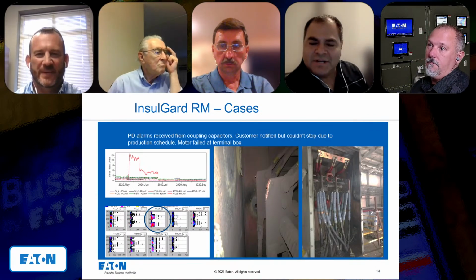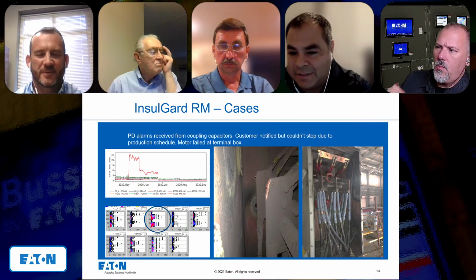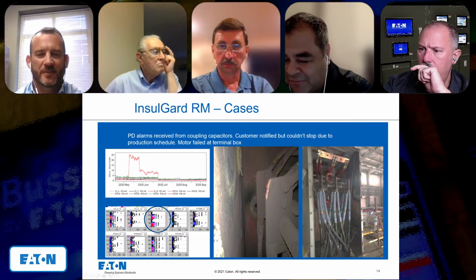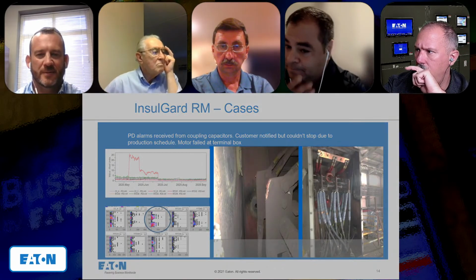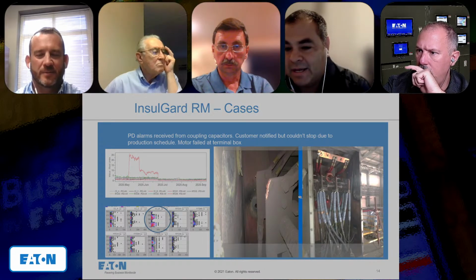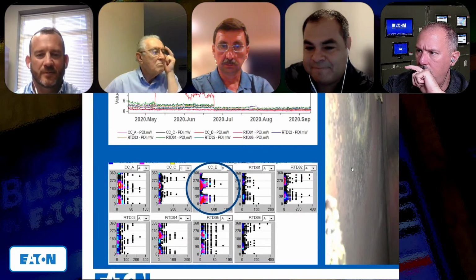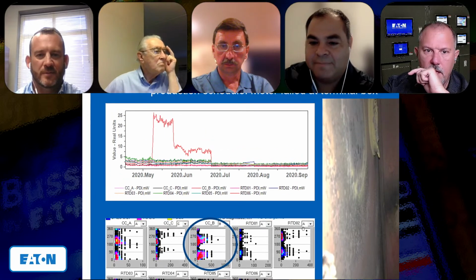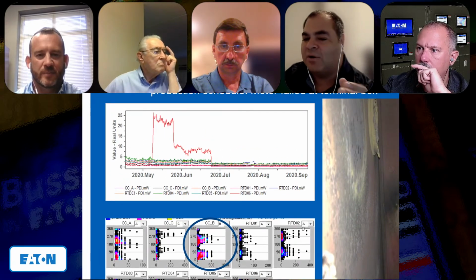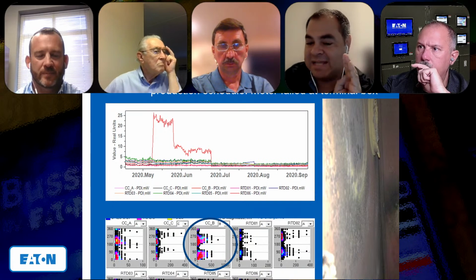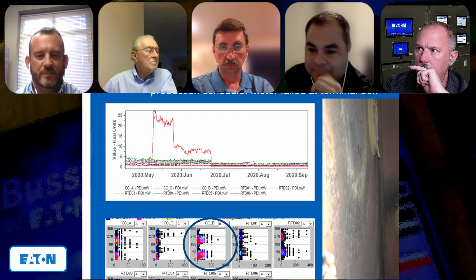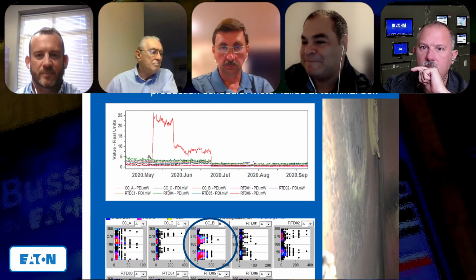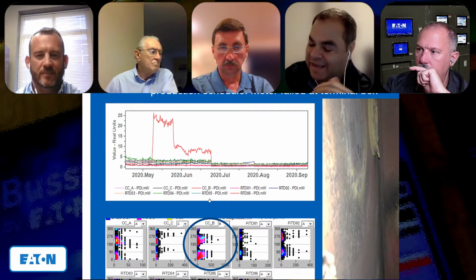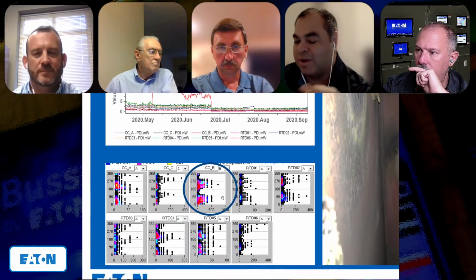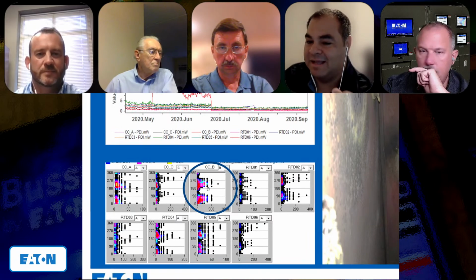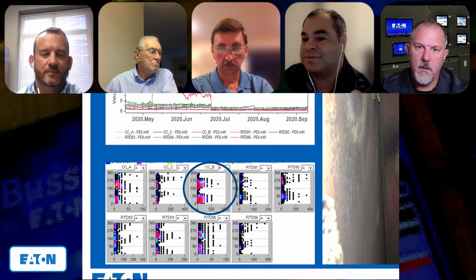This is another case, very interesting. This is a motor, a 15 megawatt motor, 13 kilovolts. You can go to the trend, please. This is a motor with very low PD intensity, and suddenly we have this trend change. It's a no-brainer, something's going on there. When we look at the graph below, we confirm it's PD occurring in the terminal box.